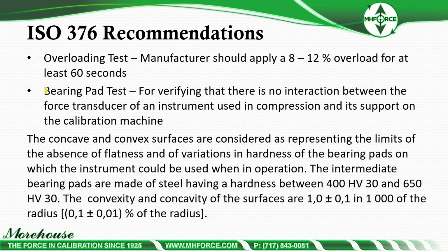Bearing pad test. This one's an interesting test. If you're using critical applications or you want to know how good your load cell is, this test is for verifying that there is no interaction between the force transducer of an instrument used in compression and its support on the calibration machine. The concave and convex surfaces are considered as representing the limits of absence of flatness and variations in hardness of the bearing pads on which the instrument could be used when in operation. The intermediate bearing pads are made of steel having a hardness between 400 HV30 and 650 HV30. The convexity and concavity of the surfaces are 1 plus or minus 0.1 in 1,000 and a radius of 0.1 plus or minus 0.01% of the radius.